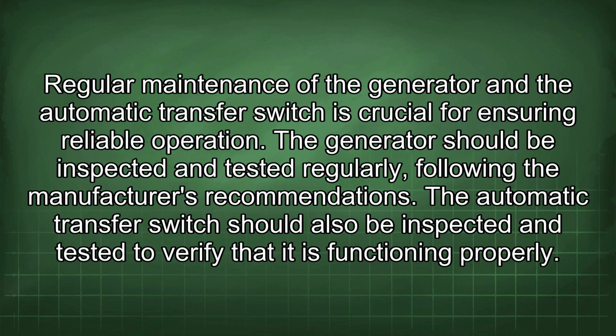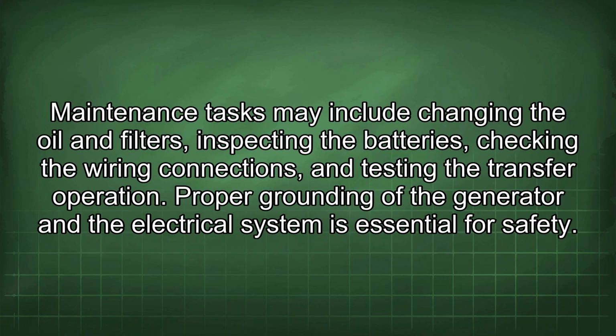Regular maintenance of the generator and the automatic transfer switch is crucial for ensuring reliable operation. The generator should be inspected and tested regularly, following the manufacturer's recommendations. The automatic transfer switch should also be inspected and tested to verify that it is functioning properly. Maintenance tasks may include changing the oil and filters, inspecting the batteries, checking the wiring connections, and testing the transfer operation.